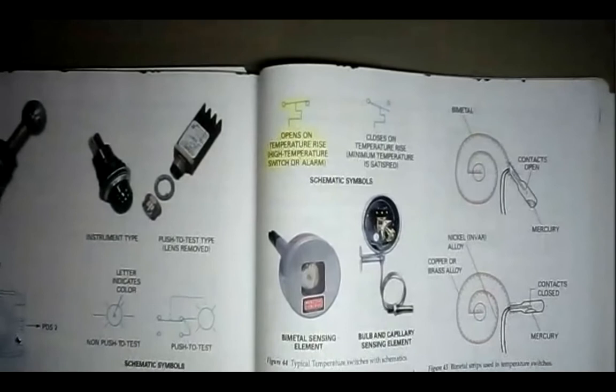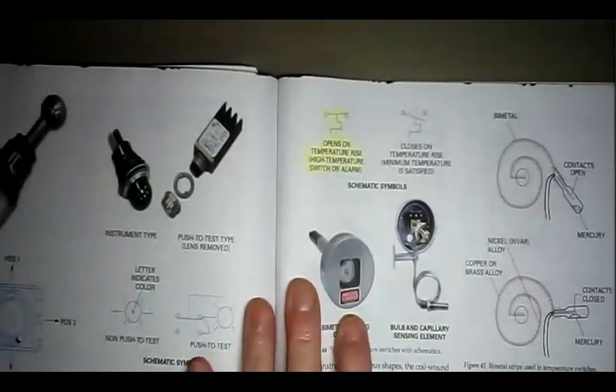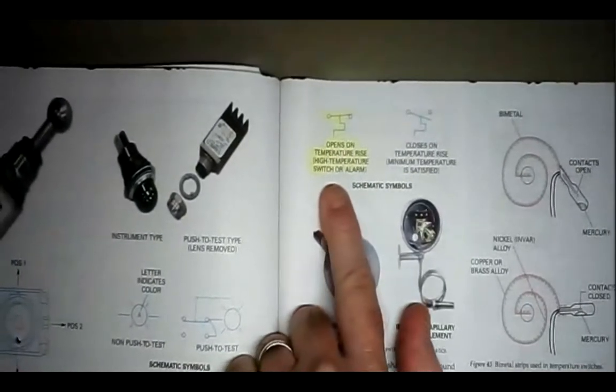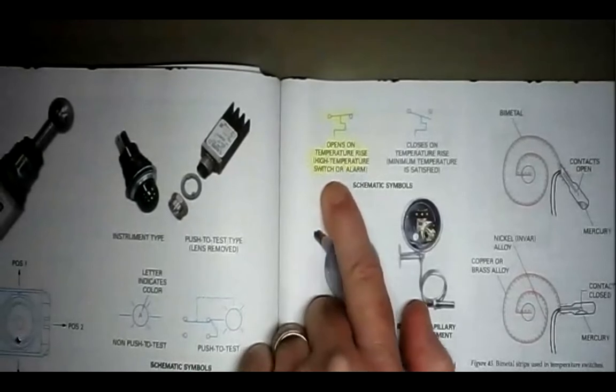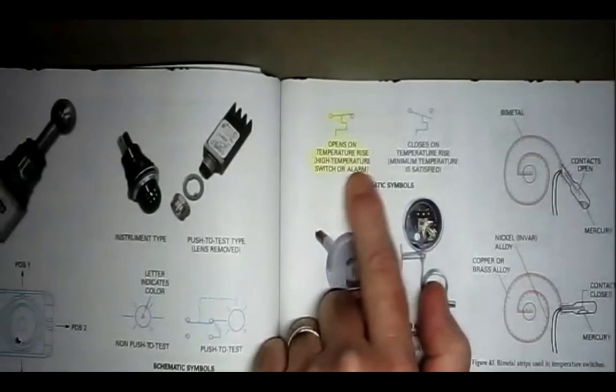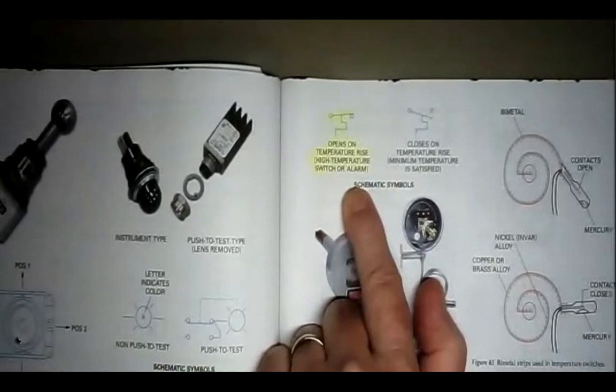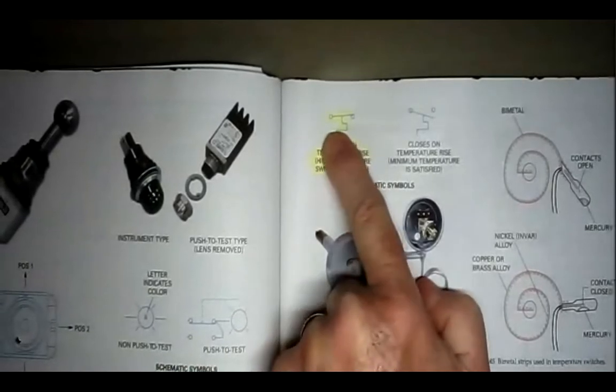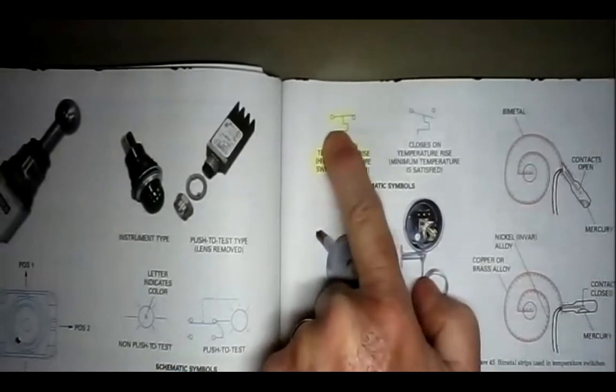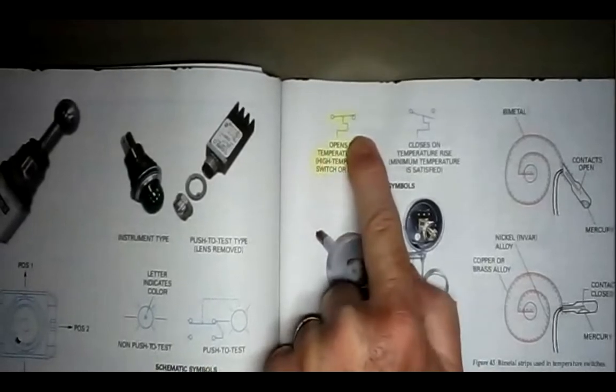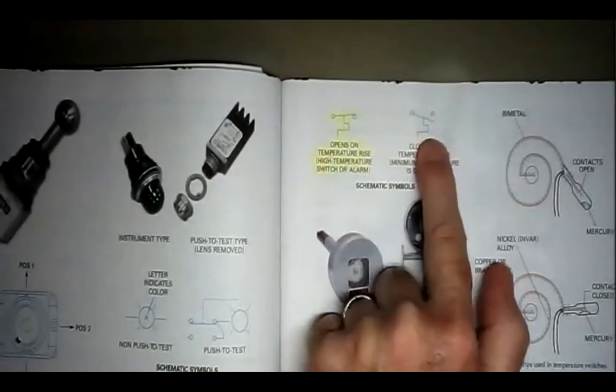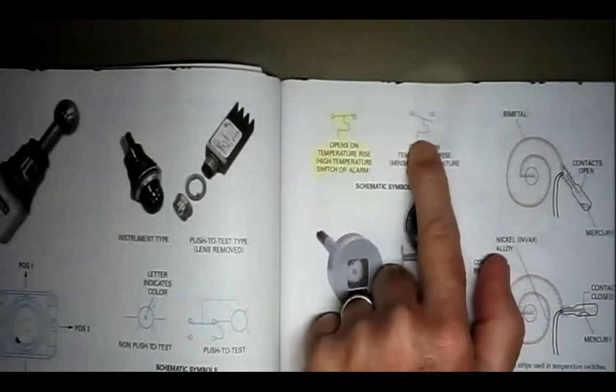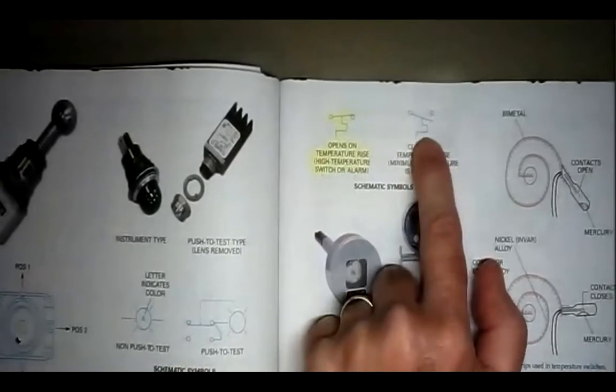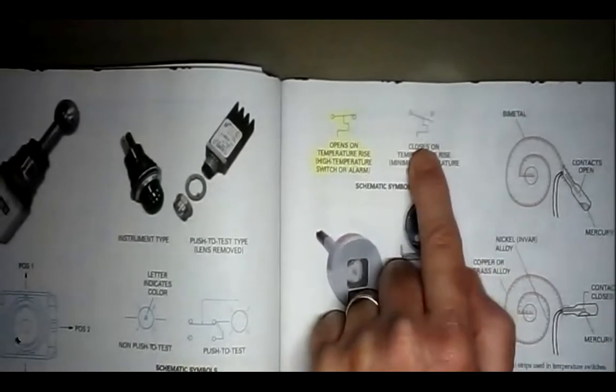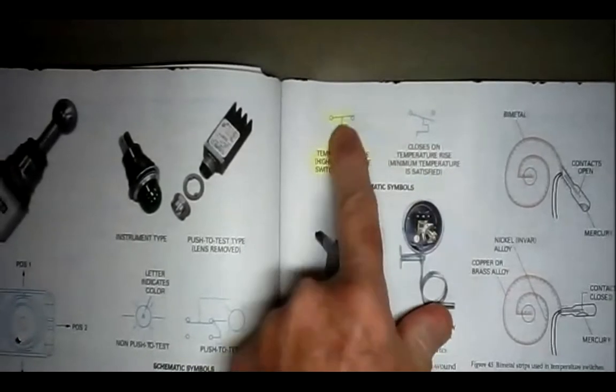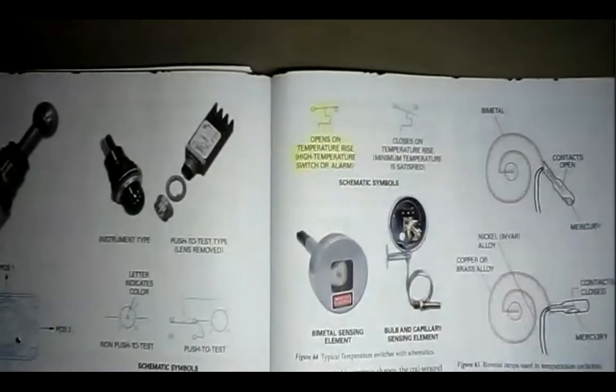Over on page 41, they're talking about a temperature switch. This is the schematic for a normally closed temperature switch. It opens on temperature rise. Higher temperature, the switch or alarm. So that's a normally closed. We know it's a normally closed because the contact bar is on top of the node. Normally open, the contact bar is below the node. As it heats up, it would close that set of contacts. As this one heats up, it opens the set of contacts.